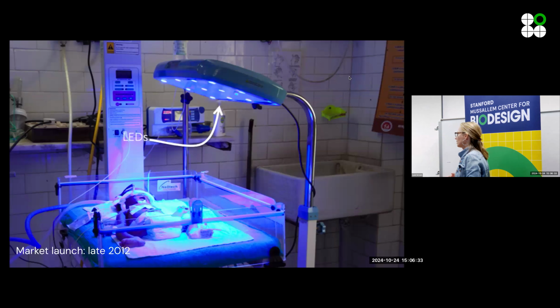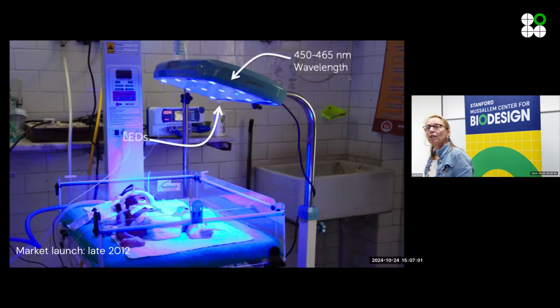It used LEDs, and so that solved this issue of bulbs getting burned out. We were not the first to use LEDs with phototherapy, but we do believe we were the first to do optical modeling. So the LED plus the lens to get an even footprint on the bed and also start to bring down the price. The other thing we learned from user research is that 20% of nurses or healthcare workers get headaches from the blue light, which is why you want to tightly contain it to the footprint of the baby.